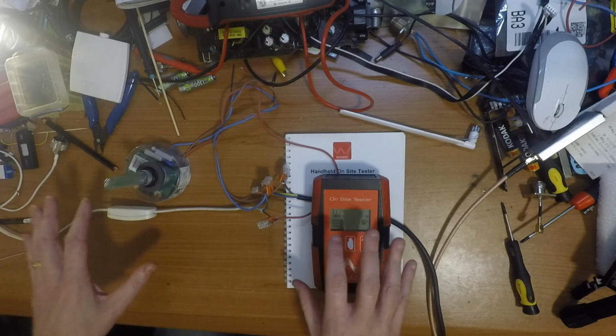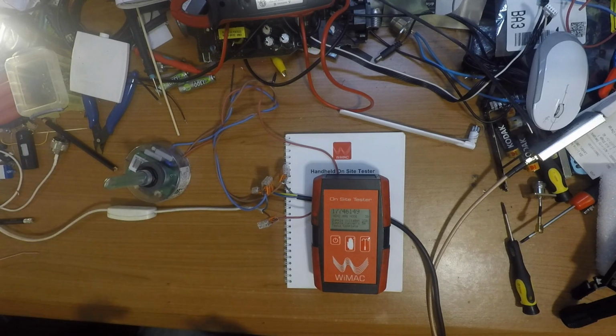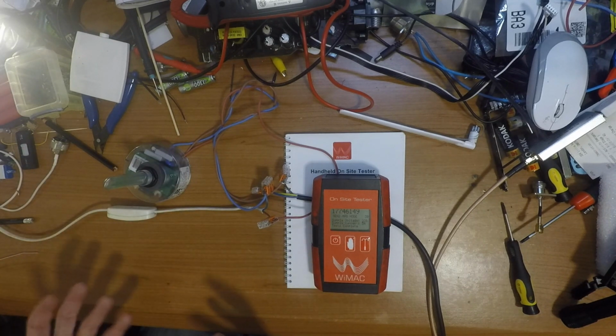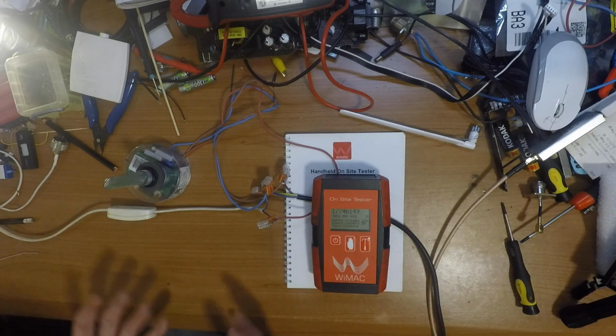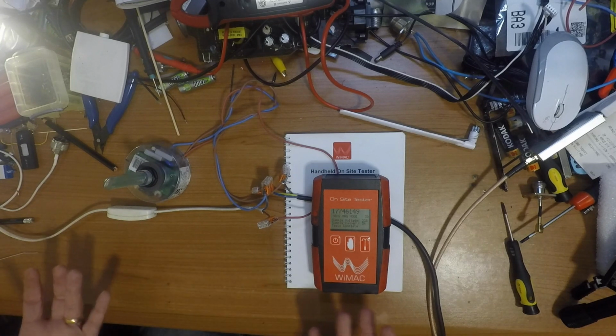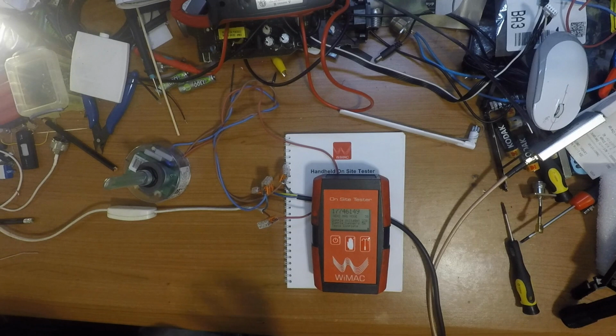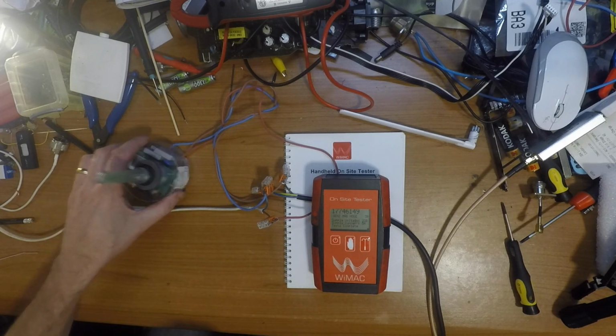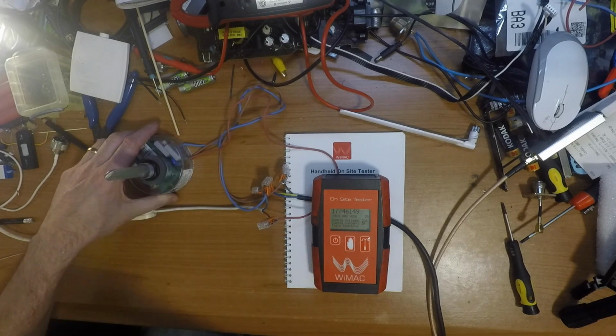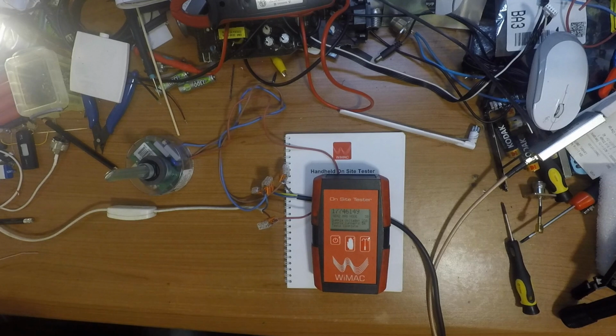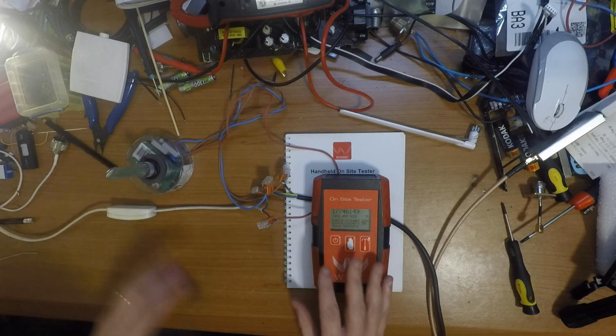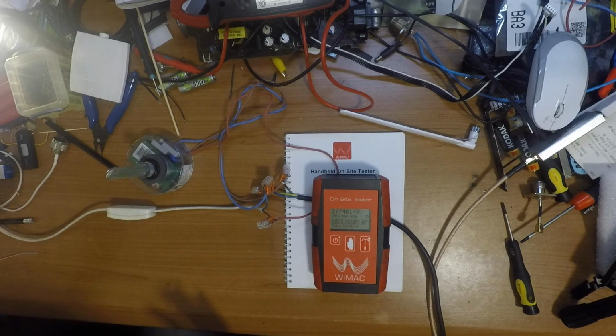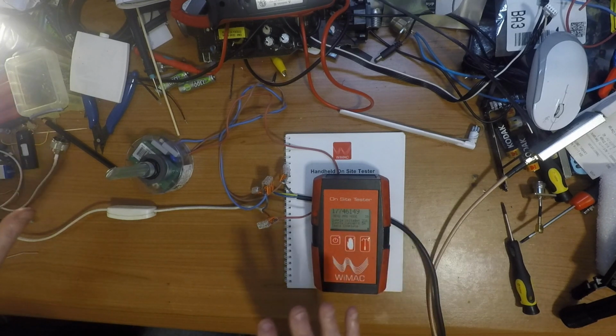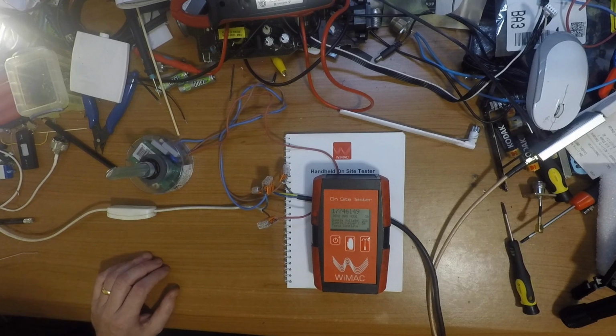The reason it takes a little bit of time is because this device doesn't want to transmit all the time. It's not allowed to. It has to cooperate with maybe hundreds of other devices all around the area. So WiMAC and LoRa and all the related protocols, LeafNet, etc., they're really, really slow. There's no way this is ever going to send CCTV images or any live data, because the network is just designed for really simple signals like light on, light off, and that's it. So now we have a power reading, and the power reading is really good, because it means that if the light should be on, but you have no power going to it, then it's faulty, and they can send an engineer out to get it fixed.